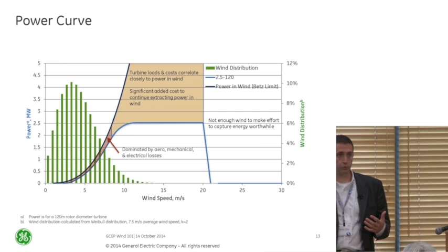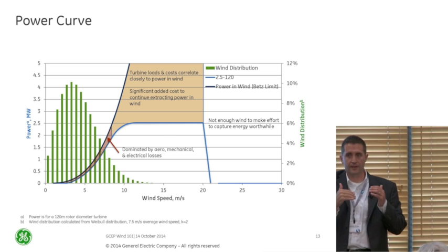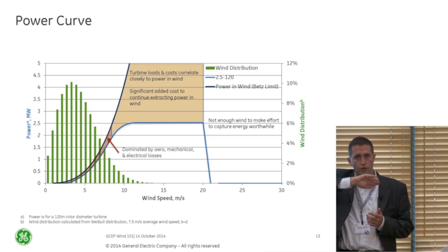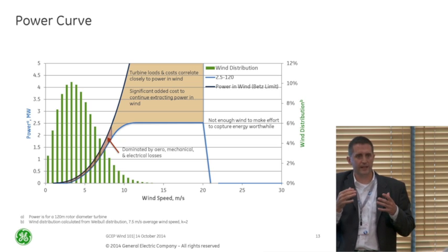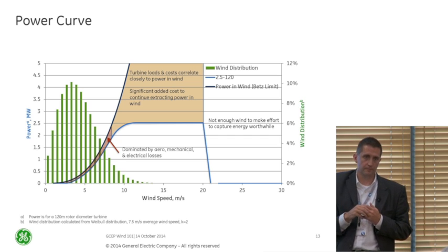And that's an important point. There's one other little thing that goes on here. You would expect this to be a nice sharp point that came over and closed off. But in order to minimize some of the thrust that we see on a wind turbine, we have what we call a peak shaver, which is going to shave and curve that place off so we can handle some of the load changes between those regions a little bit better.